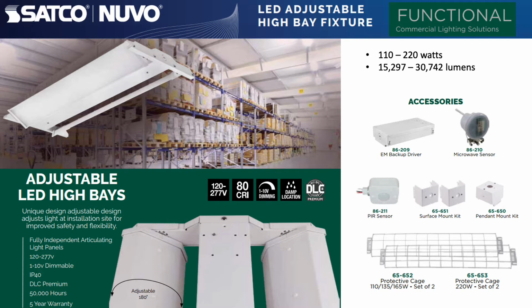For accessories, we have a battery backup add-on, sensors, either microwave with 5 adjustments or a standard PIR motion detector. For mounting, included are chains, and options are pipe mount, surface mount, and also protective cages for additional fixture safety. The fixture is dimmable using 1 to 10 volt technology. It's made for indoor use and has a rating of IP40, and it is DLC Premium certified to enhance your utility rebate where applicable.